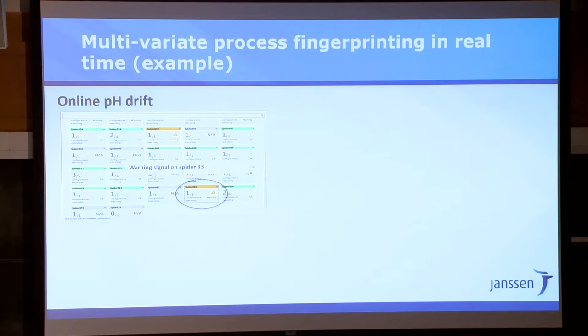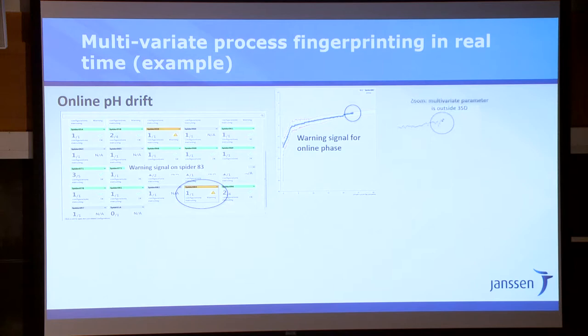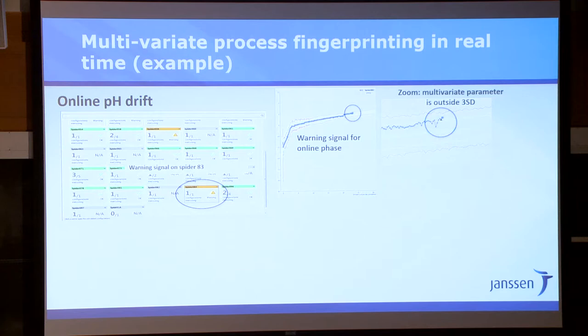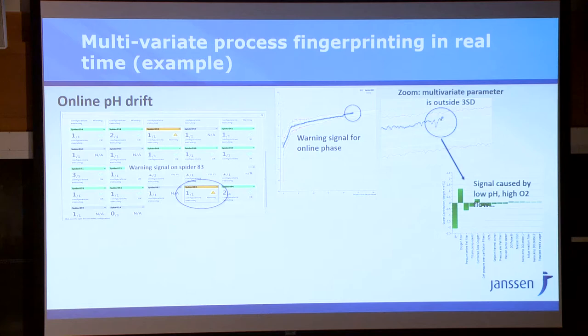We're using more and more this fingerprinting. Here's another example of pH drifting — you start getting out of your plus/minus three sigma and you get the alarm. You can then go into all the variables and it's going to tell you which variables are causing this. The key one here is one particular pH probe that is drifting. We have a backup probe that's still okay, and we have some offline measurements. So we know exactly what to do — we need to just switch out that probe and change it.